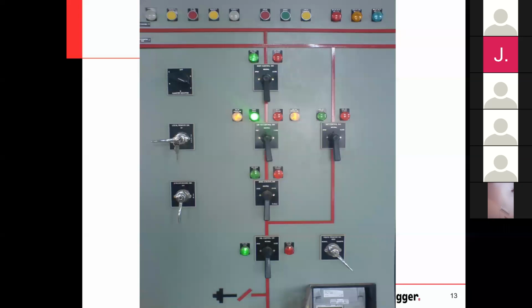To eliminate this confusion, we have a separate switch called local remote. That means control panel or SCADA. If the switch is in CP, no one can operate from remote. If the switch is in SCADA, no one can operate from the push buttons available in the panel. Sorry, these TNC buttons, trip and close buttons. So that's the reason you have another switch here.